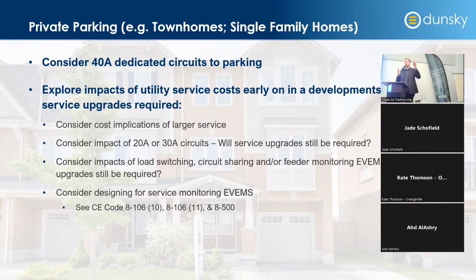If it's just a one-car garage, you can get away with a 20 amp circuit to that garage — that's allowable within Toronto's performance requirements. A lot of people don't think of that for EV charging, but 20 amps is less than 40 amps, so that can be a way to handle your EV charging loads. Maybe that'll solve the problem.